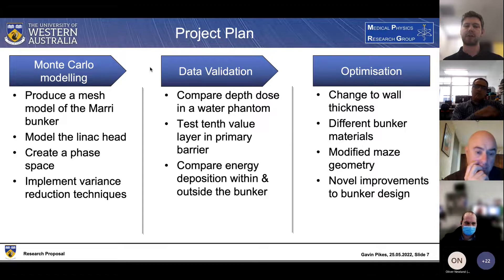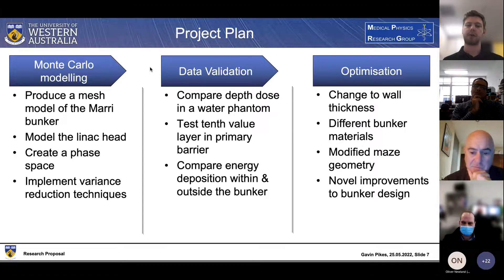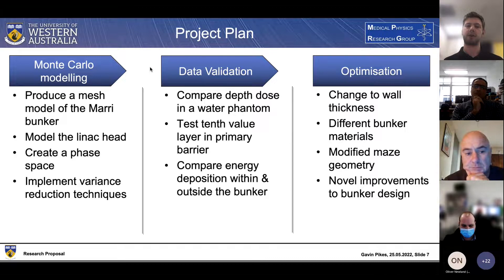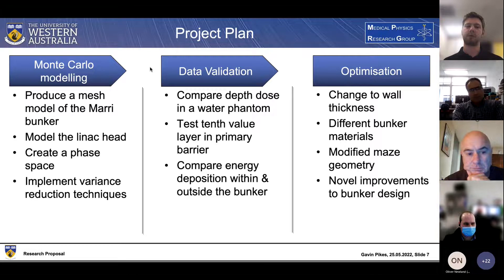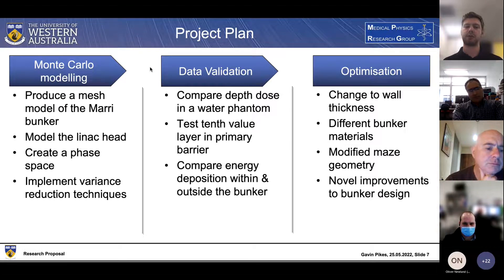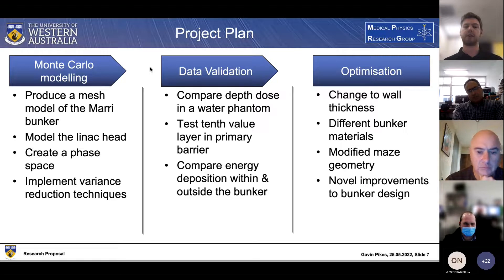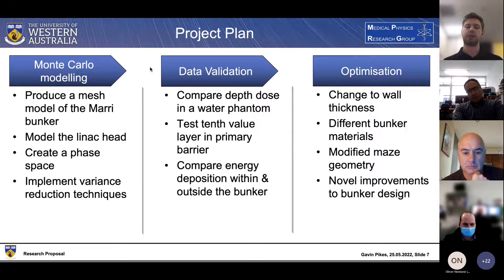Moving on to data validation, there are three main methods: first, comparing the depth dose in a water phantom between our simulated and measured results; then looking at the tenth value layer in our primary barrier from our Monte Carlo simulation versus documented values; and finally comparing the energy deposition within and outside the bunker between our Monte Carlo simulation and radiation survey results.